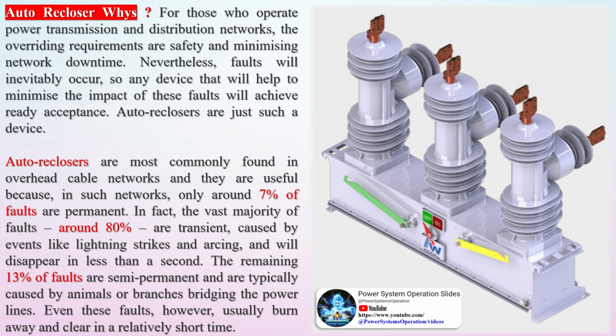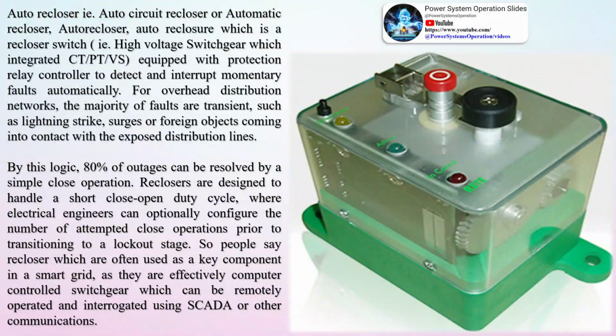Faults are inevitable, but devices like auto-reclosers help mitigate their impact. Auto-reclosers are particularly useful in overhead cable networks, where only about 7% of faults are permanent. The majority, around 80%, are transient and clear quickly, while the remaining 13% are semi-permanent and typically resolve in a short time. Auto-recloser, i.e. auto circuit recloser or automatic recloser, which is a recloser switch, i.e.